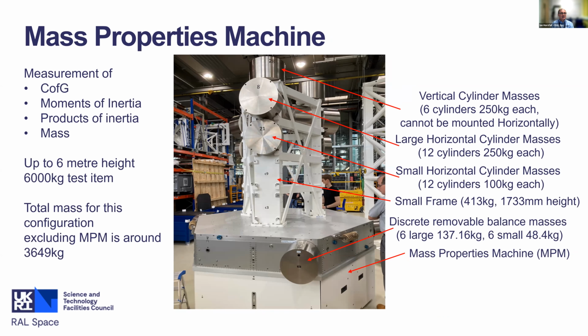You sit the test item on top, and it's then very, very gently wobbled so that it sits on air bearings, and it moves backwards and forwards, only about 5 millimeters. And it does that in 5 degrees of freedom. So it rotates and it wobbles in 2 directions as well. It can slide in 2 directions. And this allows the machine to deconvolute those accelerations and work out the mass properties of the test item sat on top.